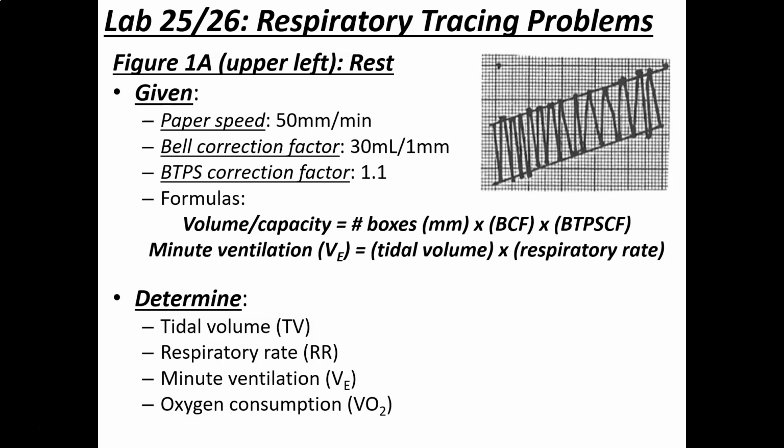And again, even though we have these normal respiratory up and down movements, right, we see that the bell is going down and losing volume because our tracing is over time going up, which is reflective of the bell losing volume. So it's natural. It should happen. We want it to happen. We don't want the CO2 to build up. We don't want to run out of oxygen.